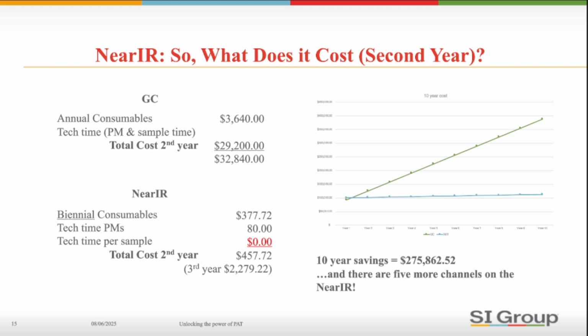Also, take into consideration that this example is just for one channel of the NIR. There are 5 more channels to use. However, since the basic system has already been purchased, any additional monitoring point only needs the purchase of fiber optic cables and a probe, a cost of approximately $18,500. For a second GC, you will have to pay full price. So what do you think your manager might say now?